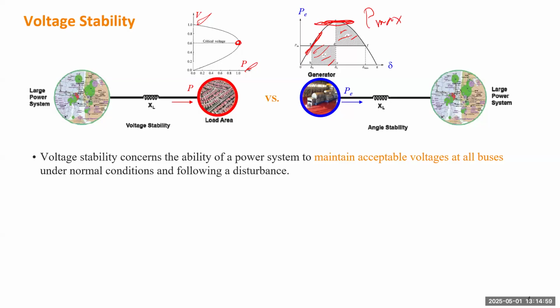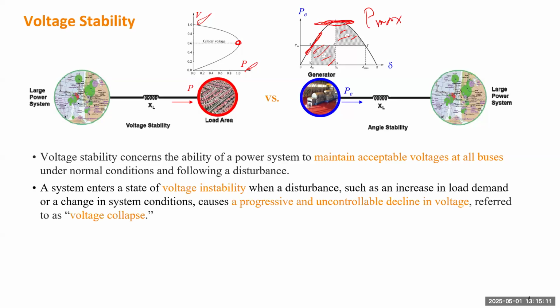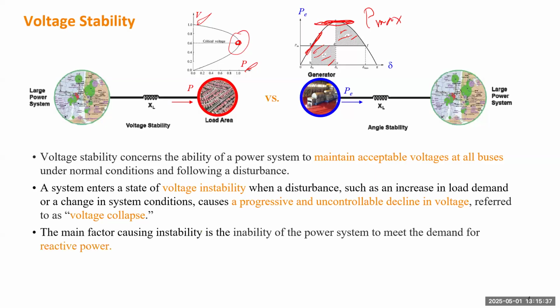Voltage stability concerns the ability of a power system to maintain acceptable voltages at all buses under normal conditions and following a disturbance. A system enters a state of voltage instability when a disturbance, such as an increase in load demand or a change of the system condition, causes a progressive and uncontrollable decline in voltage, referred to as voltage collapse. Voltage collapse is a phenomenon, but what happens here is really related to voltage instability. The main factor causing instability of voltage is basically the inability of a power system to meet the demand for reactive power. Later we'll explain why having reactive power can effectively prevent voltage collapse.